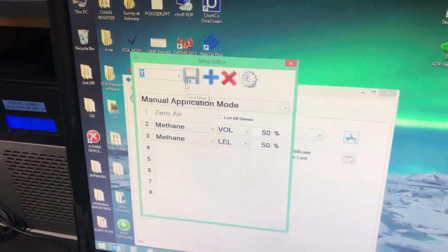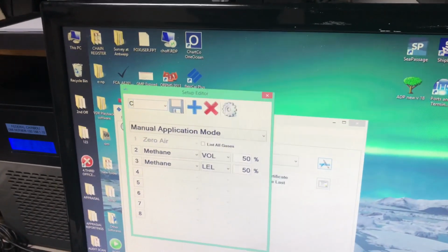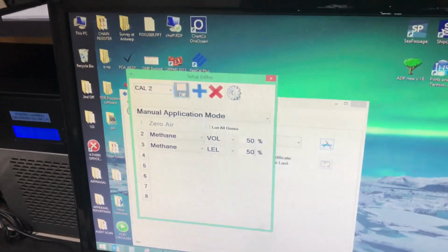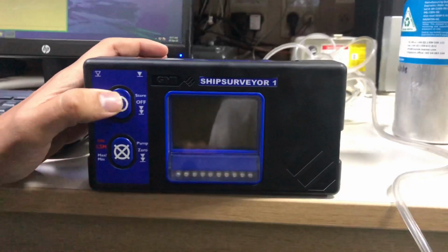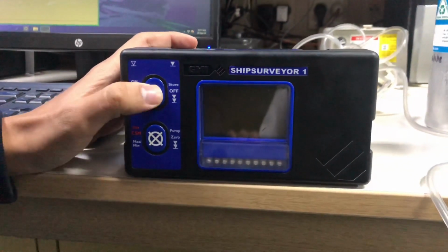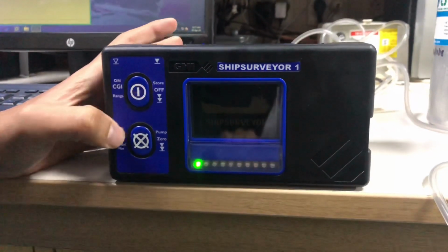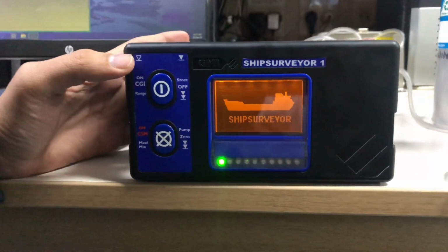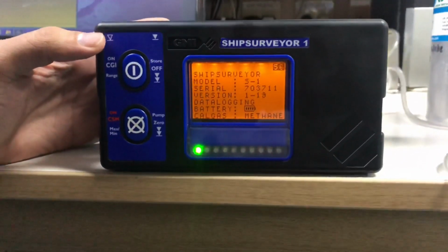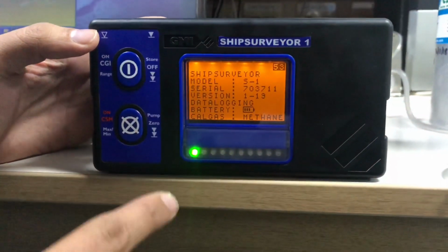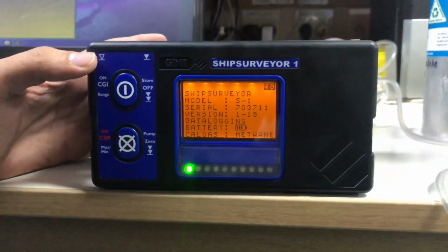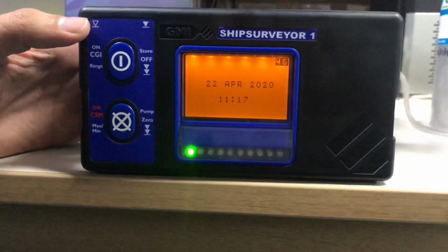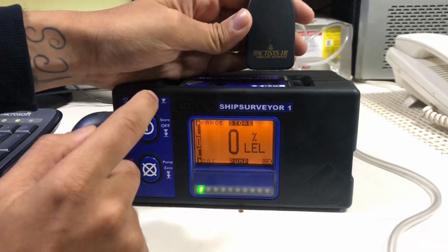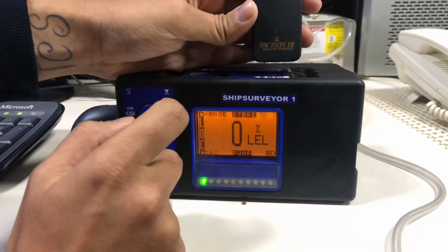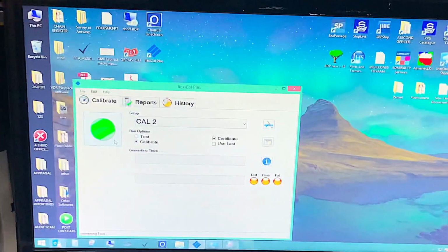You can save by whatever name you want, but I'm saving it as calibration 2 and save the settings. Let's start with the calibration process. Switch on the equipment. It will show the model number, serial, calibration gas, battery. Make sure this infrared controller is held at least 2.5 centimeters above the reception sensor. So let's start with the calibration.